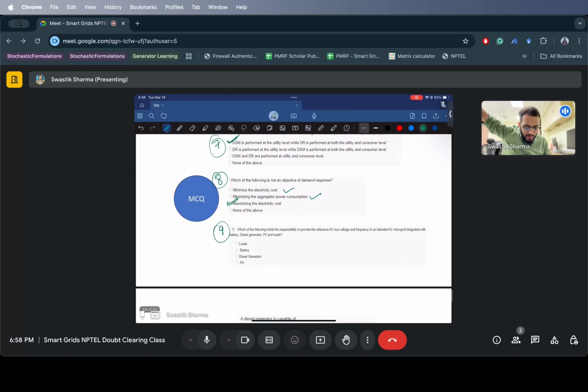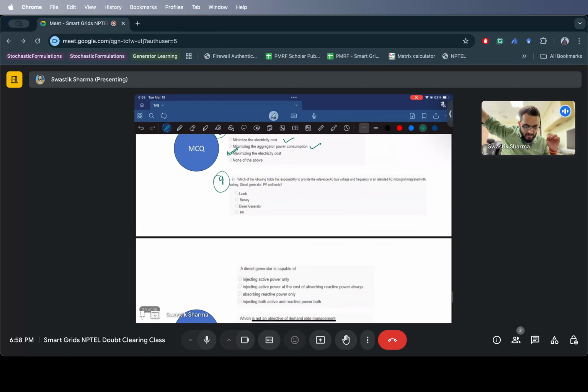Ninth: which of the following holds the responsibility to provide the reference AC bus voltage and frequency in an islanded AC microgrid? This was discussed last time, and the correct answer is the diesel generator, because you can control the output so it constantly provides and holds power at that point, and it can also provide inertia. Loads, battery, and PV are not used for this if you have an islanded microgrid with battery, diesel generator, PV, and loads.